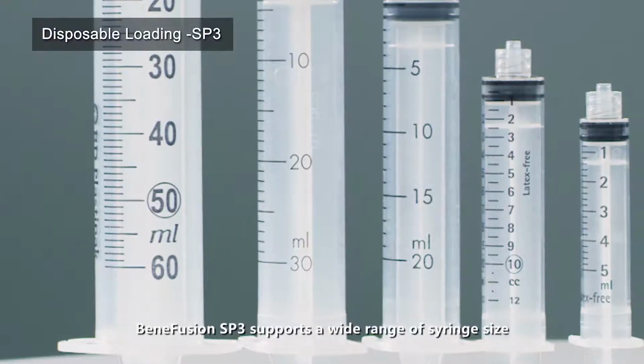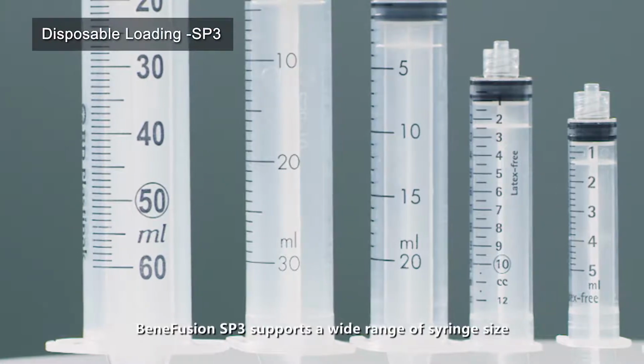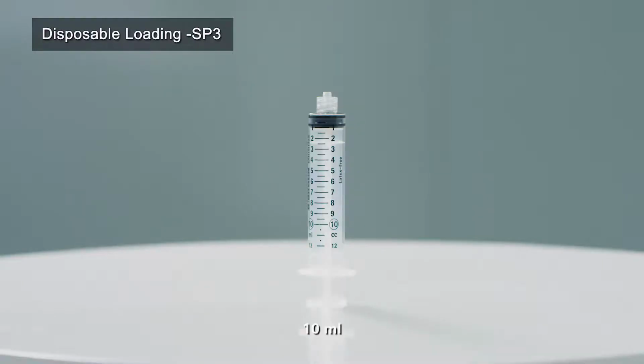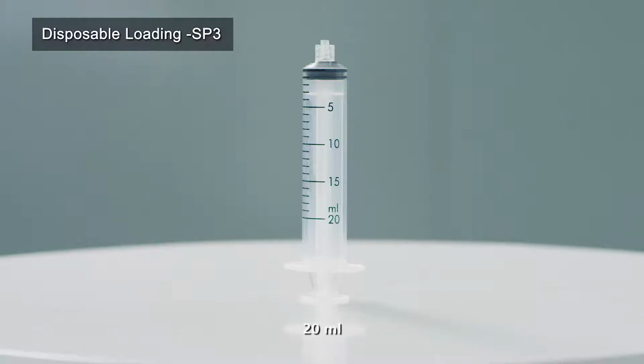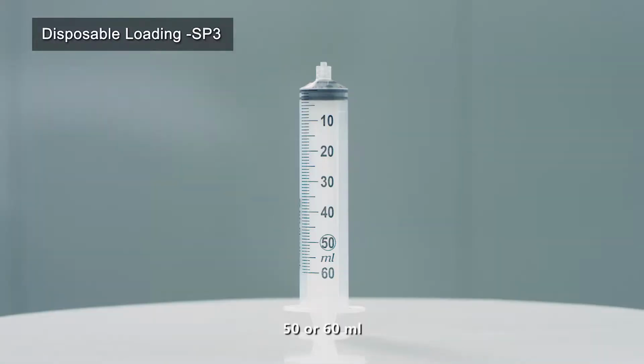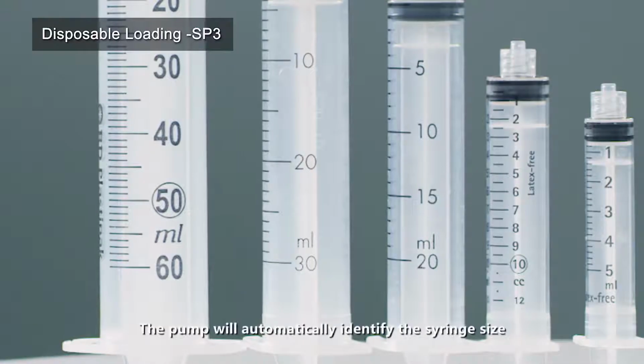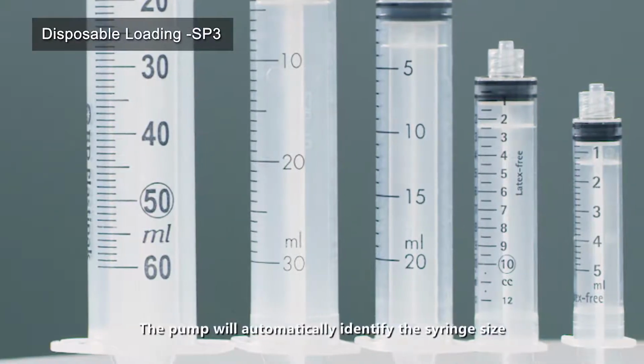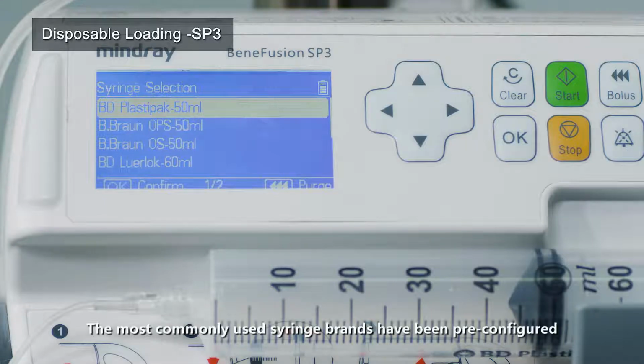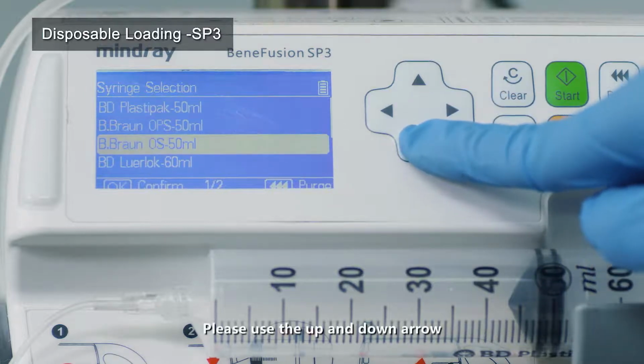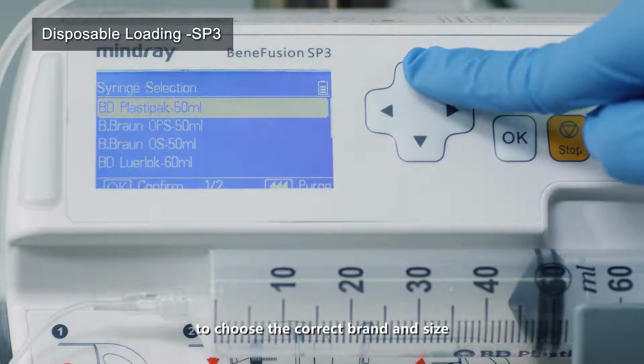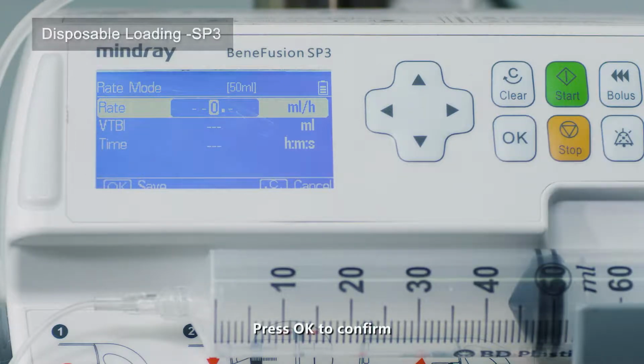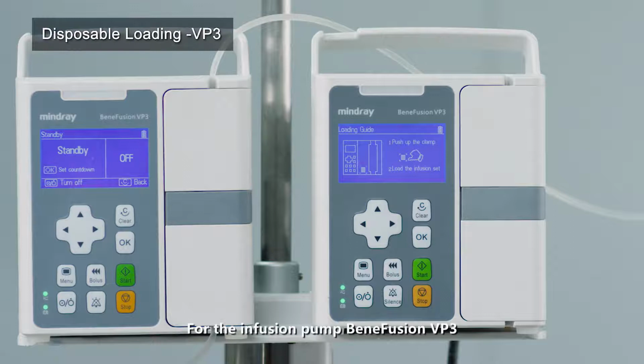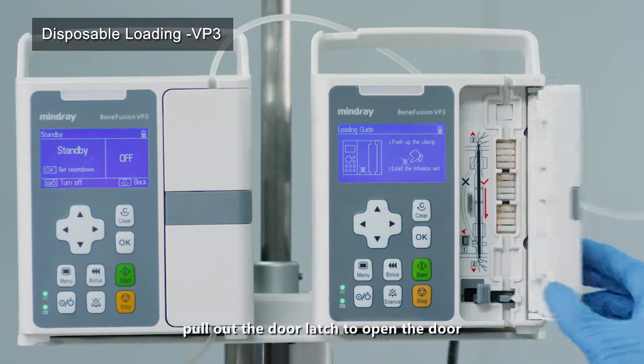BeneFusion SP3 supports a wide range of syringe sizes: 5 milliliter, 10 milliliter, 20 milliliter, 30 milliliter, 50 or 60 milliliter. The pump will automatically identify the syringe size. The most commonly used syringe brands have been pre-configured. Please use the up and down arrows to choose the correct brand and size. Press OK to confirm.